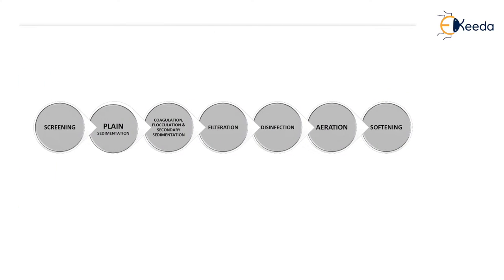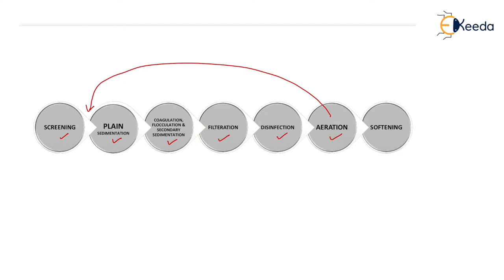The various units in sequence are: screening, then plain sedimentation, then coagulation, flocculation and secondary sedimentation, then filtration, then disinfection, and after disinfection, aeration. If the water is highly polluted, we will do the aeration process as the second process before the plain sedimentation to improve the efficiency of the plain sedimentation tank. After disinfection and aeration, the last process is the softening process which will remove the hardness of the water. We will now see each step and process in detail, starting with the screening process.